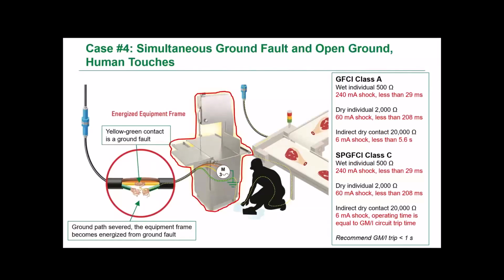Now looking at the final case, considering the ground fault and the damaged or open grounding conductor all happening at the same time, along with human contact on the piece of equipment. So we can see that the Class A GFCI and the Class C special purpose GFCI will react in similar timeframes for both the 500 ohm and the 2000 ohm body impedance model calculations. And that's because both devices are based on that same inverse time curve from UL 943.